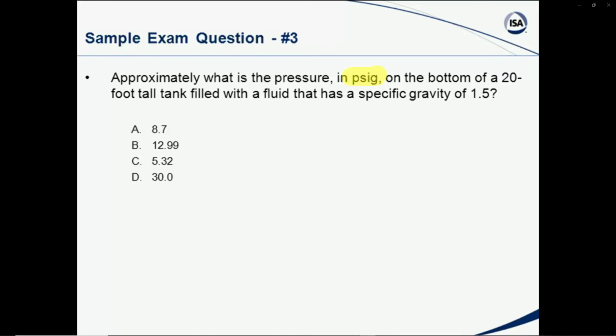And so I'm letting you sit there and look at this and say, what would be the first thing that I would do to solve this problem? Well, you remember I said the specific gravity is super important. And here we have 20 feet of liquid head, but it's also equal to 1.5 specific gravity, so that's going to give me 30. 20 feet times 1.5 is 30. Well, look, I have an answer D.